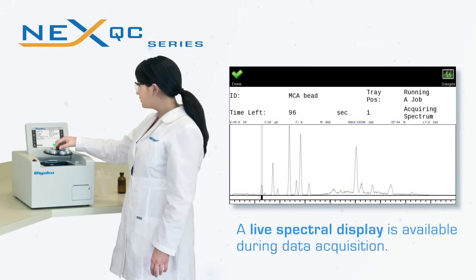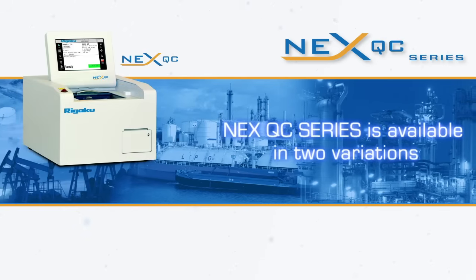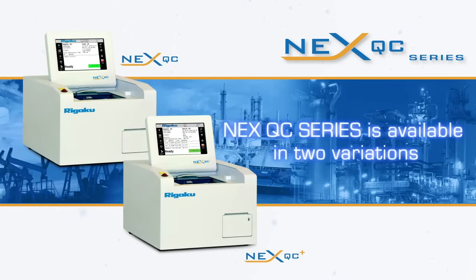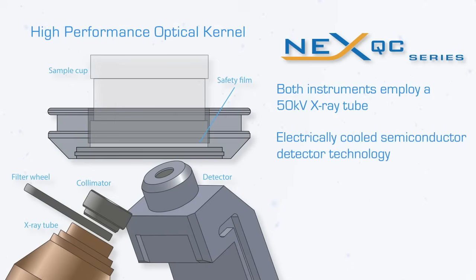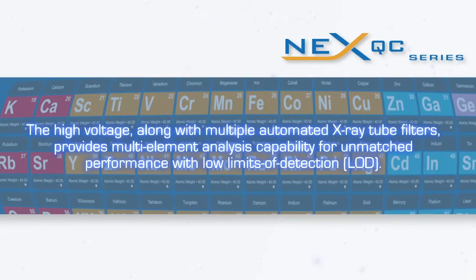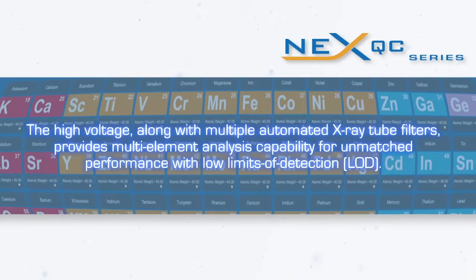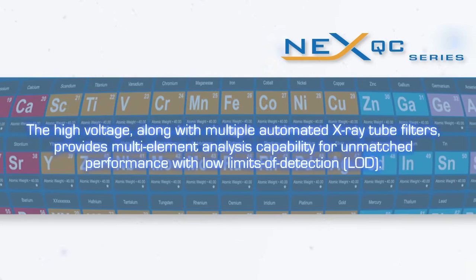A live spectral display is available during data acquisition. The NEX QC series is available in two variations: the low-cost NexQC and the high-resolution NexQC Plus. Both instruments employ a 50,000-volt x-ray tube and electrically cooled semiconductor detector technology to deliver exceptional short-term repeatability and long-term reproducibility with excellent element peak resolution. The high voltage along with multiple automated x-ray tube filters provides multi-element analysis capability for unmatched performance with low limits of detection.